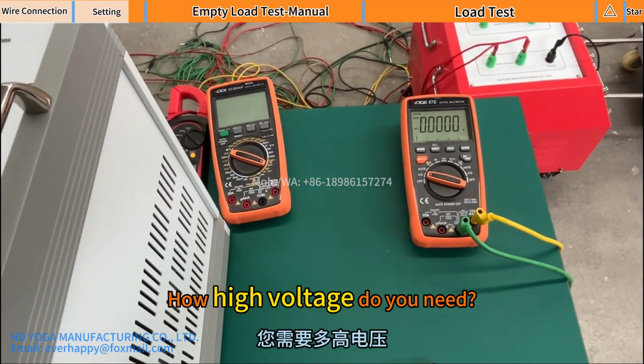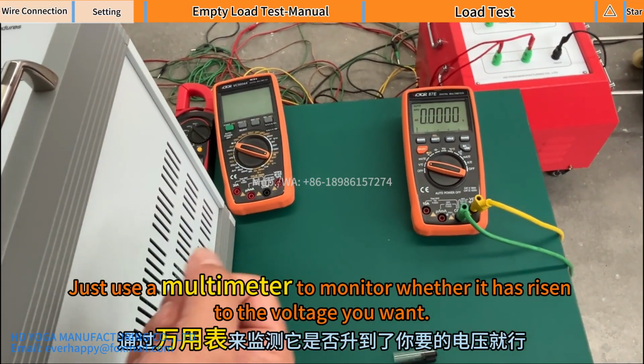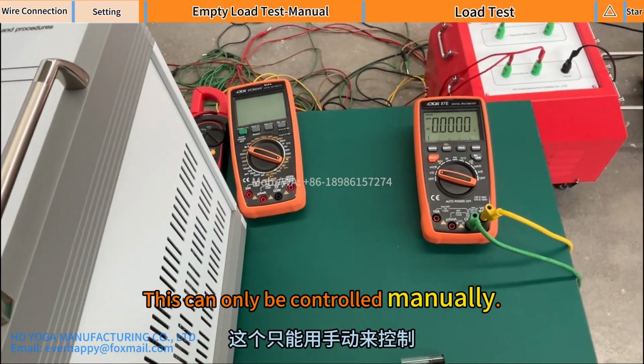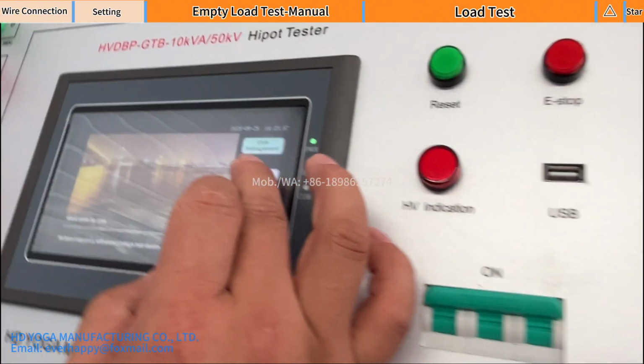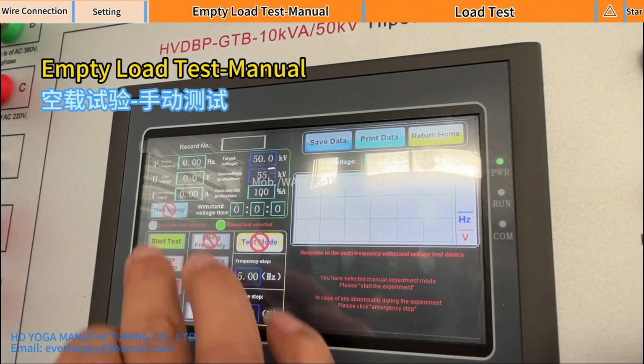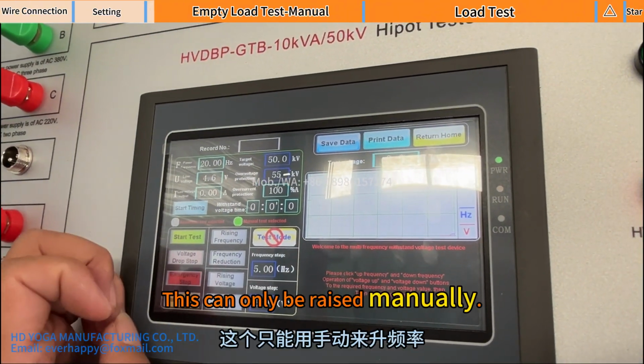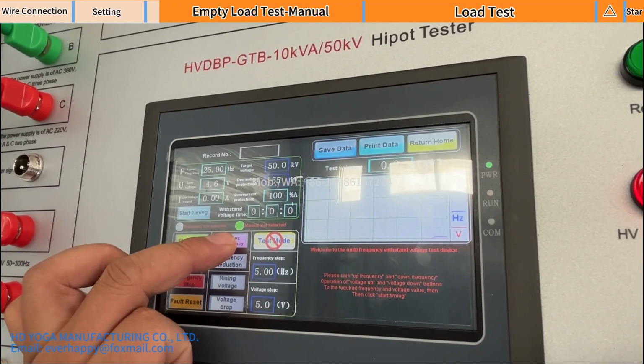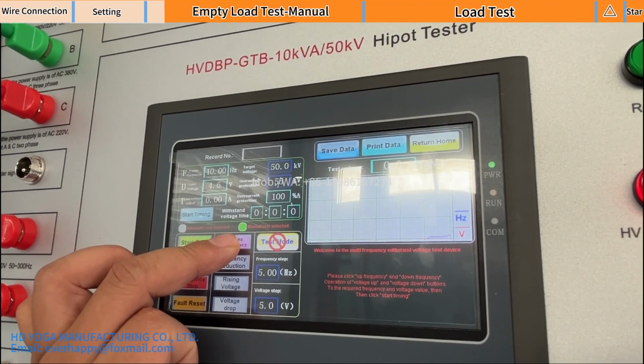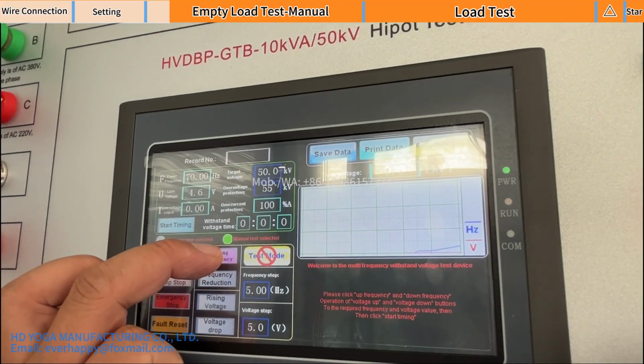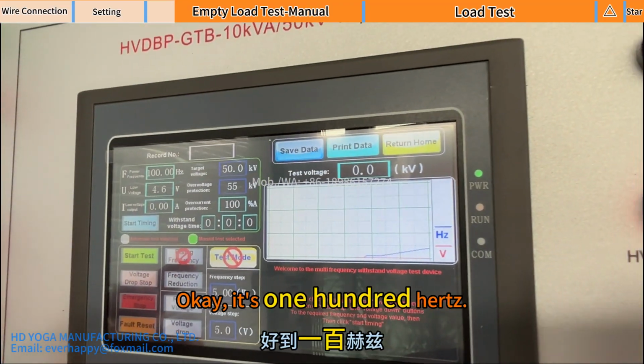How high voltage do you need? Just use a multimeter to monitor whether it has risen to the voltage you want. This can only be controlled manually. Go back and use manual directly. Click Start Test. This can only be raised manually. Raise the frequency to 100 Hz. Hold it on. Okay, it's 100 Hz.